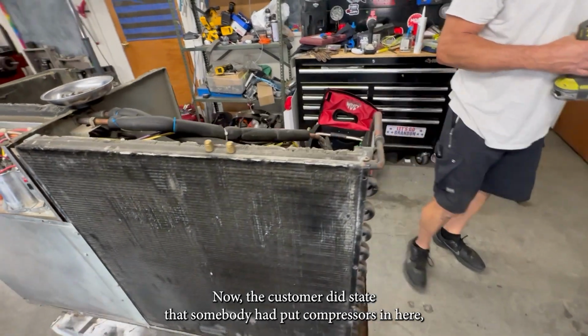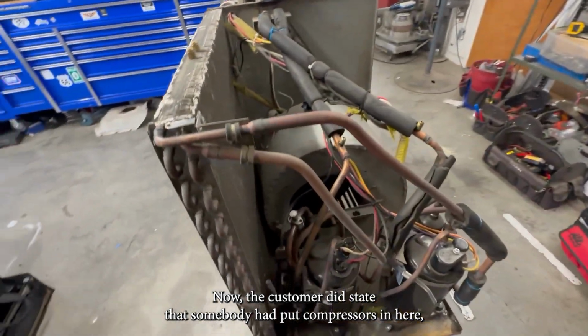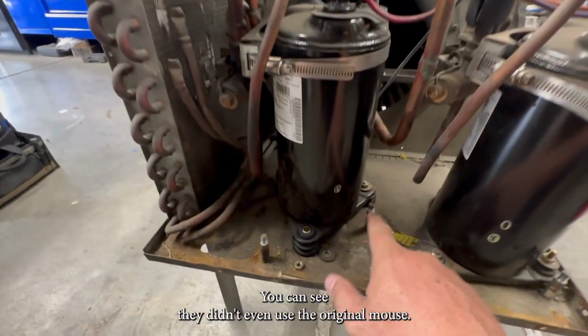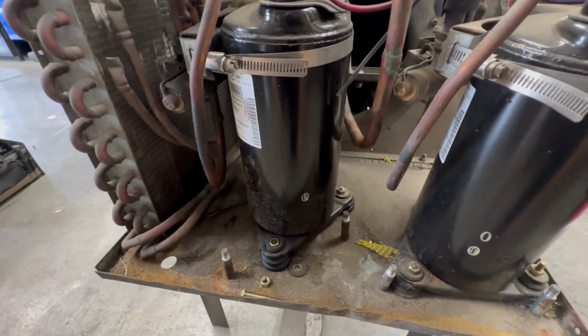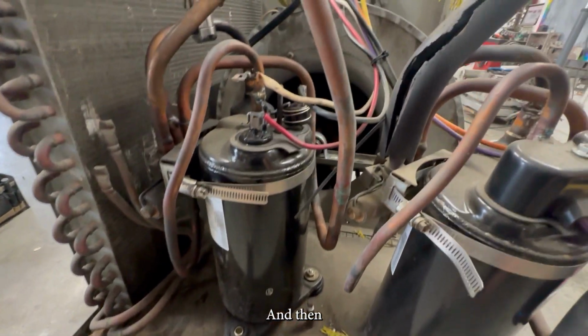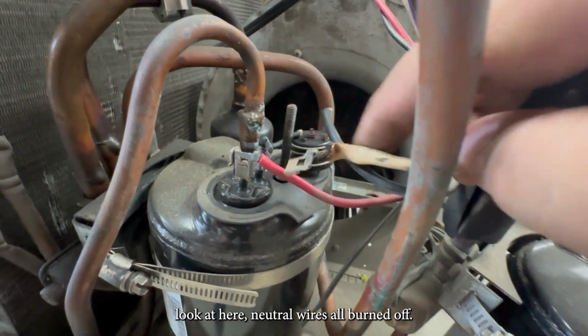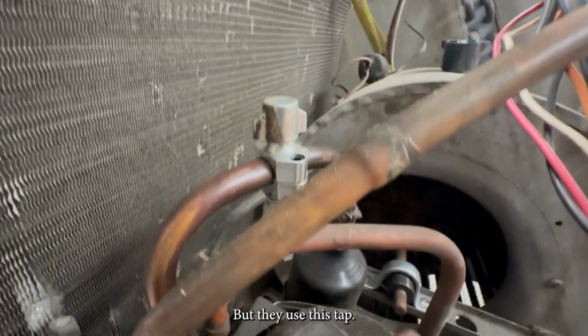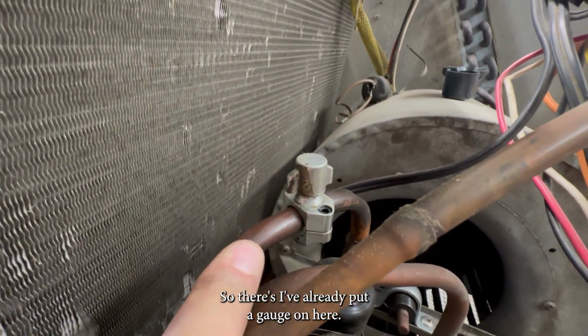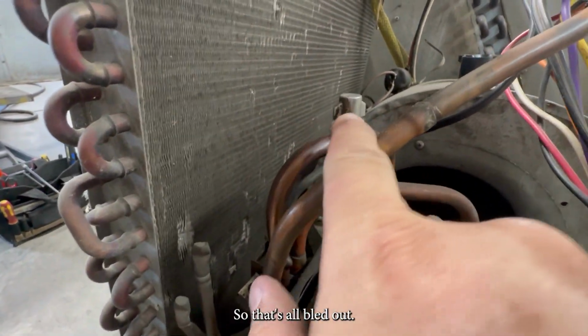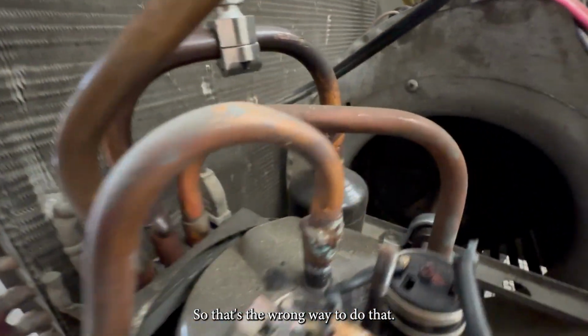The customer did state that somebody had put compressors in here, which they did. You can see they didn't even use the original mounts. And look here, neutral wires all burned off, but they used this tap. You can see where the oil is. I've already put a gauge on here - there's no Freon in this system, it's all bled out. So that's the wrong way to do that.